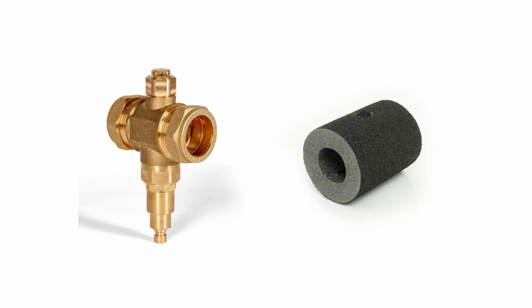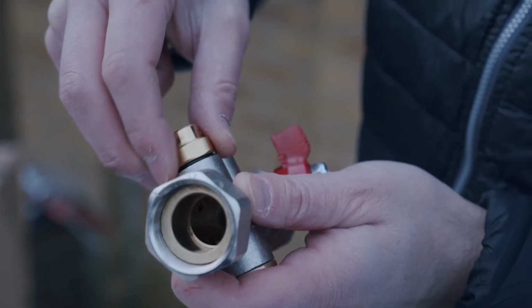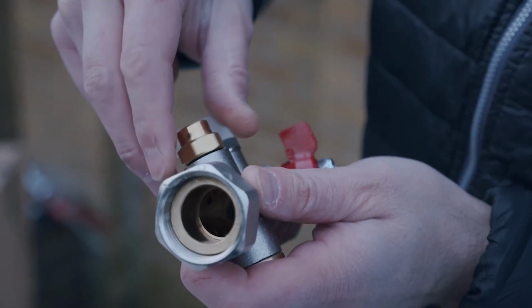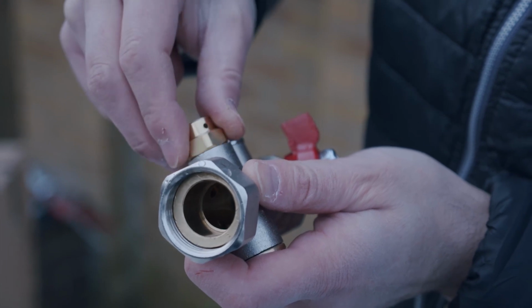The Daikin Altherma hybrid monobloc comes with a number of features to prevent water freezing in the pipework and heat pump. For worst case scenarios of power loss in cold weather, 2 types of passive protection are available. Daikin recommend using antifreeze valves instead of glycol in most circumstances. Glycol reduces the efficiency of a heat pump system and only protects to a temperature corresponding to the dosage level of glycol. Instead, Daikin recommend the use of antifreeze valves, which automatically drain the pipework so they cannot freeze.